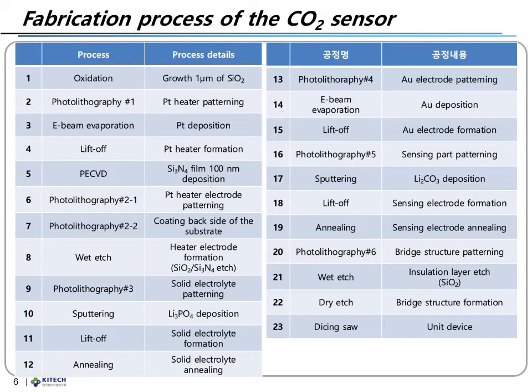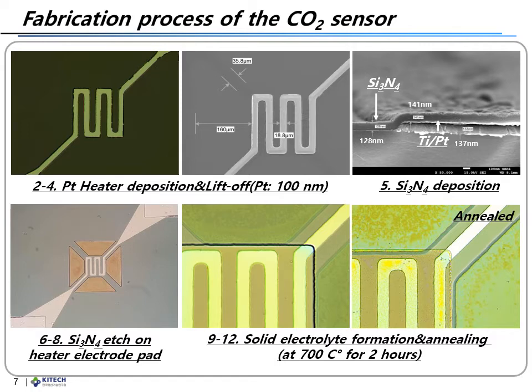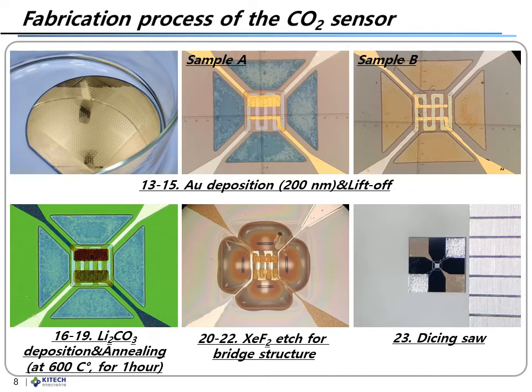The fabrication process consists of 23 steps including 7 photolithography steps using a photomask. First, wet oxidation of 6-inch silicon wafers was conducted. A platinum heater was deposited on the substrate and covered with silicon nitride. The lithium phosphate was patterned and annealed on the heater. Gold electrodes were deposited and lithium carbonate formed on one side of the gold electrodes. Xenon difluoride etch was performed to make a bridged structure to reduce heat sink through the silicon substrate. Finally, dicing saw cut the wafer into unit sensors.